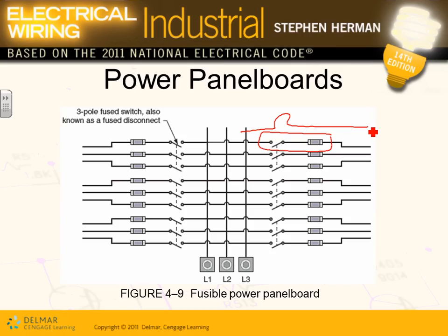The advantage of circuit breakers, guys, is you can reset them if they trip, for the most part, right? That's the advantage versus fuses. If they open, what do you need to do? You're going to go unplug it and plug in a new one. The other advantage for circuit breaker panels is they're smaller in size. So this is a circuit breaker panel. If it was a fuse switch, it would be twice as big as that.